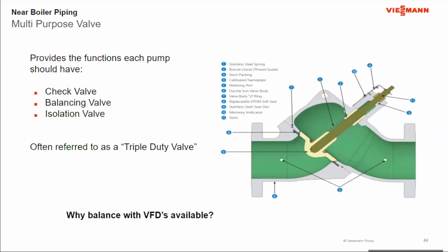I look at a lot of drawings. The drawings will have an isolation valve and they'll also show a check valve. In the multifunction valve, it operates as an isolation valve. It also operates as a check valve. But the third function is it also operates as a balancing valve. And it does it all here through a single step. So if I bring it all the way down and bring it down tight, it becomes my isolation valve.